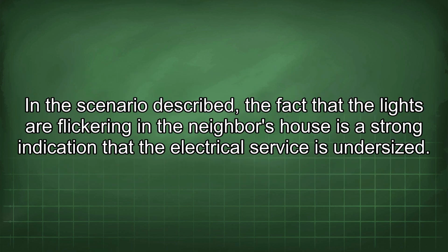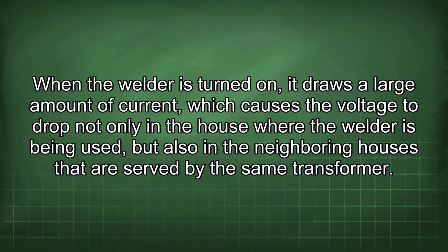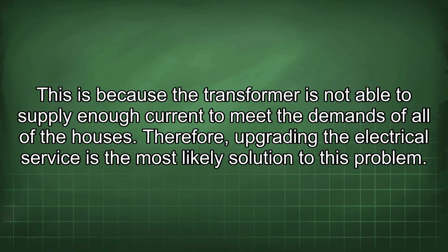In the scenario described, the fact that the lights are flickering in the neighbor's house is a strong indication that the electrical service is undersized. When the welder is turned on, it draws a large amount of current, which causes the voltage to drop not only in the house where the welder is being used, but also in the neighboring houses that are served by the same transformer. This is because the transformer is not able to supply enough current to meet the demands of all of the houses. Therefore, upgrading the electrical service is the most likely solution to this problem.